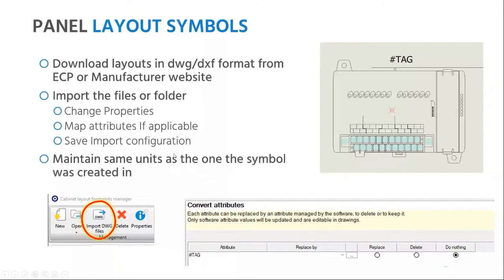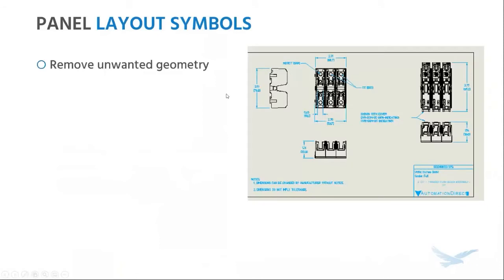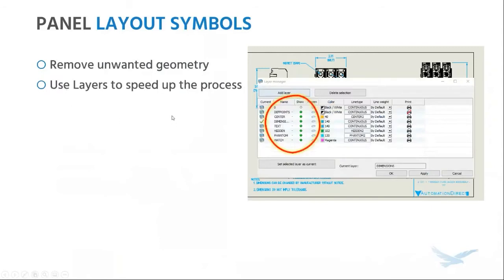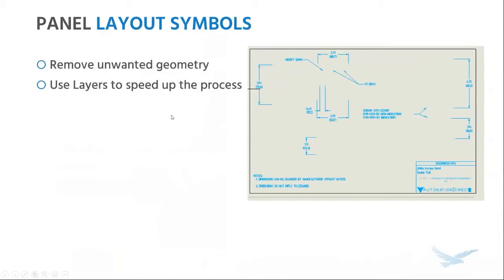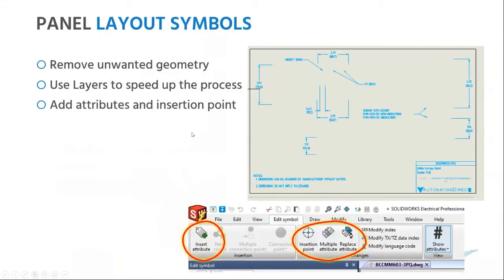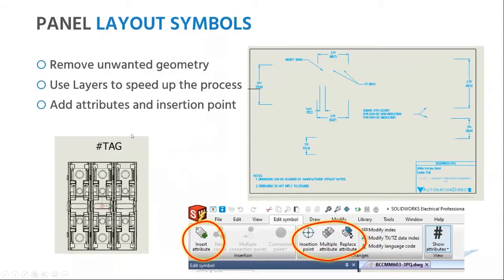If you're doing a whole lot of attribute mapping, you might want to save the import configuration as well. When setting the unit system of these symbols, you want to maintain the same units as the one the symbol was created in. Unfortunately, manufacturers will make a whole bunch of information available including other views, title blocks, and annotations that you may not want — so the first step is to remove any unwanted geometry. A lot of these unwanted geometries tend to be on different layers, so you can hide or show those layers, isolate what you don't want, and get rid of them. Once done, go ahead and add the attributes and the insertion points that you want, and you've got your perfect panel layout symbol.